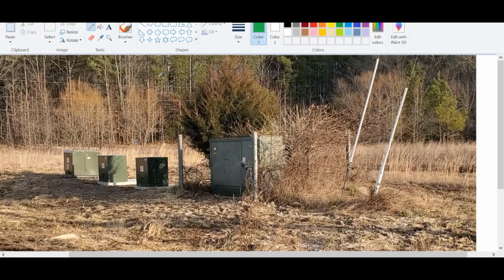So I called my Virginia Power representative and I asked them exactly what they're going to do when they put in the 3-phase service, because nobody on Mike Holt's forum could figure out what they were doing with these extra transformers. So what you got is you got your last service pole over here on the right. They come in underground with one of the phases and all the way up into the first transformer, and then they got the other phases going up into the first dummy and the second dummy case. And of course they've got the low voltage cables, the hot, neutral, hot, coming from the single phase transformer over to the building.